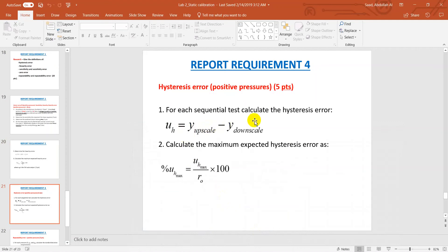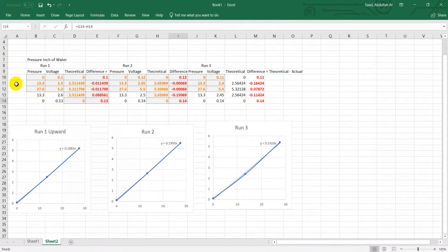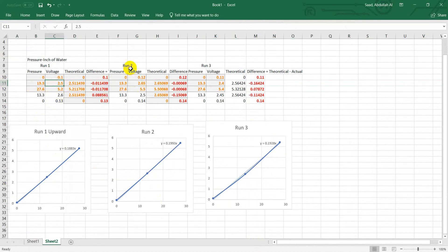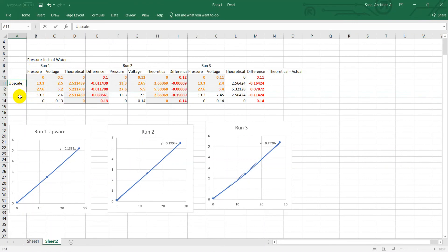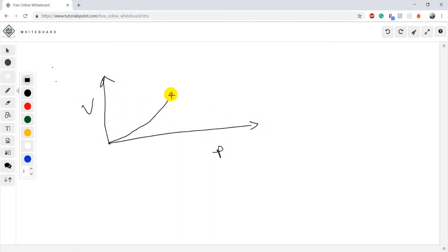After that, you have to find out the hysteresis error. The hysteresis error is the difference between the upscale and downscale readings. For example, you can see the upscale value is 2.5 for run one, 2.65 for run two, and 2.4 for run three. Let me do a sketch: if I draw a curve with voltage on one axis and pressure on the other, when going up we go this way, and when going down we may go a different way.